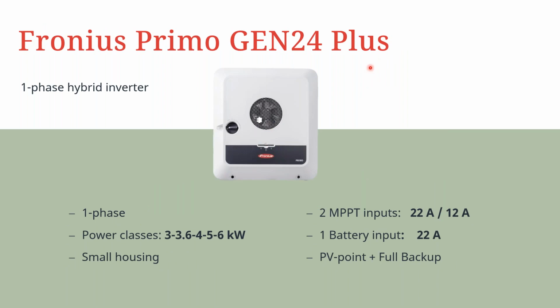Looking at further details about the variants, we have the Primo GEN24 Plus, which is the single phase hybrid inverter. The power classes for this inverter start from 3 kilowatts, then 3.6, 4, 5, and 6 kilowatts. It comes in a comparatively smaller housing when you compare it with the Symo GEN24 Plus. In terms of the MPPTs, we have the current handling capacity of 22 amps and 12 amps for the 2 MPPTs. So you can see here, one of the MPPTs has a higher rating than the other, and the battery input is at 22 amps. This therefore means that with this Primo GEN24 Plus, you get the PV point, which is the optional power or opportunity power, plus the full backup when you have a battery storage integrated.